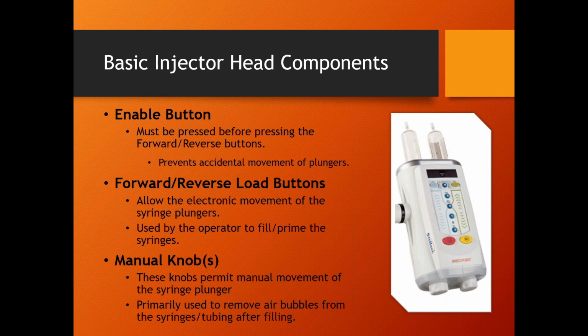This contrast injector is like nothing else. It doesn't have manual knobs. It doesn't have forward and reverse buttons. If my syringe is at 100 milliliters and I want to back it up 5 milliliters and move it forward 2 milliliters, too bad. Should have thought ahead. You have to shut the whole thing down, make it restart, take all the tubing off, and there's a lot of tubing. It's a great injector. It's just totally different, and that's why it's weird.